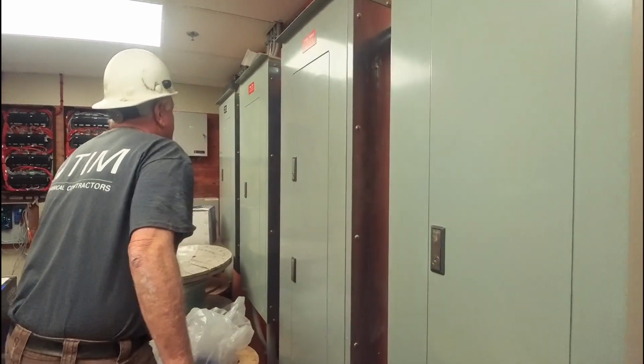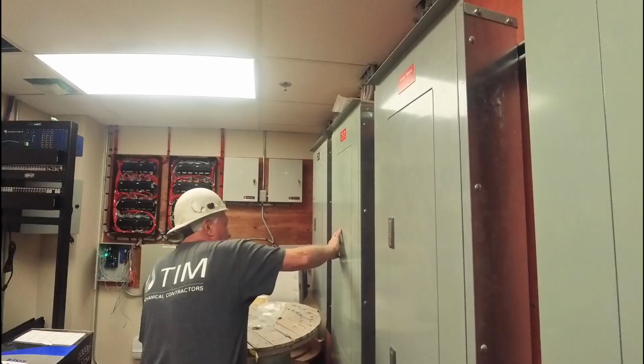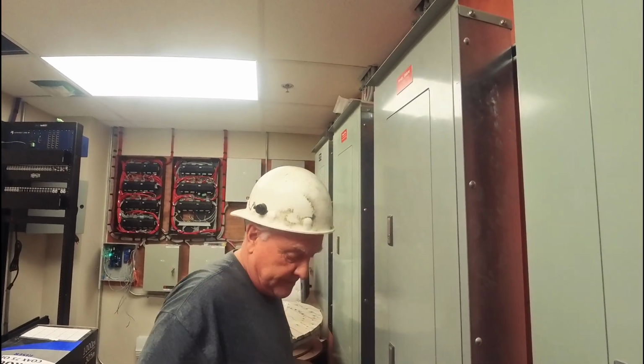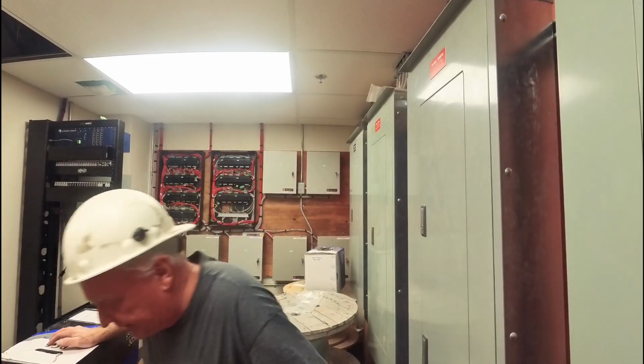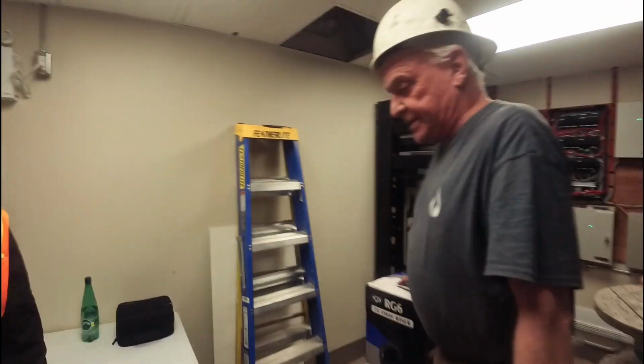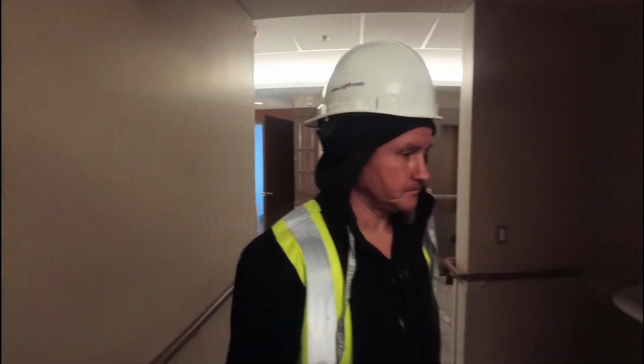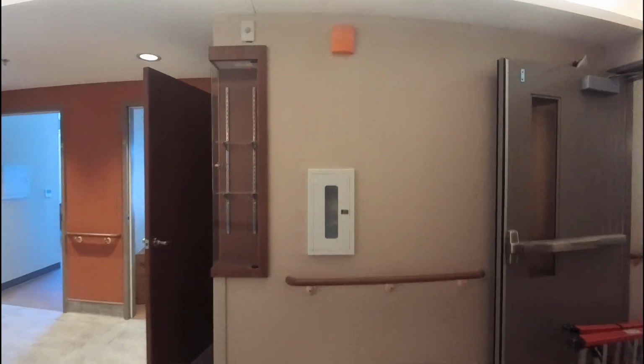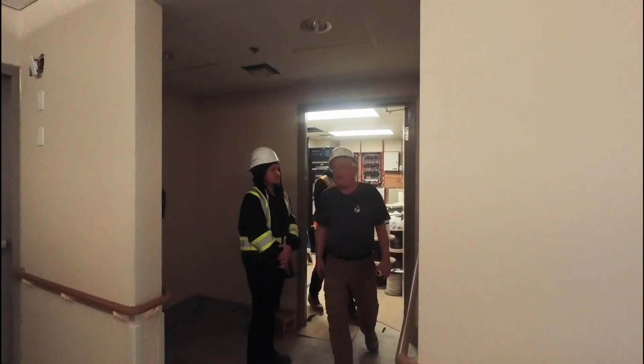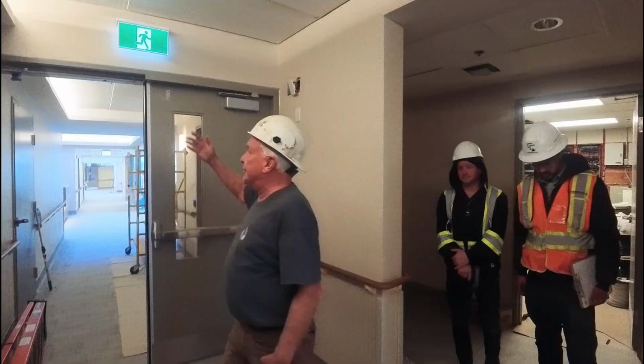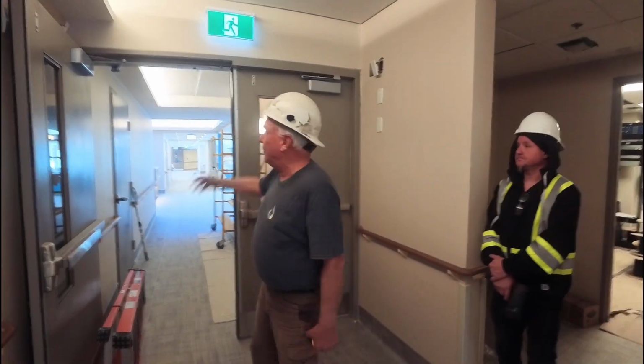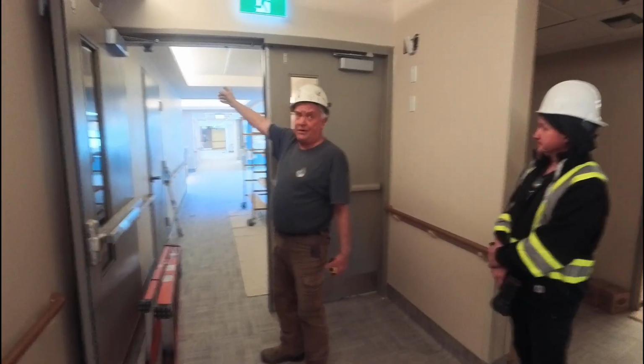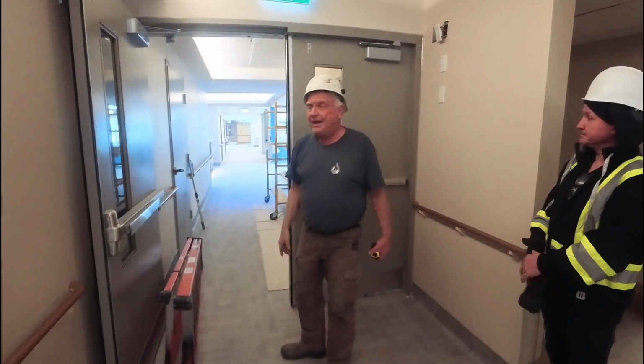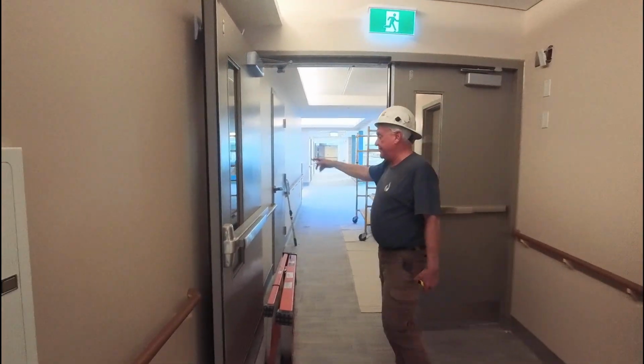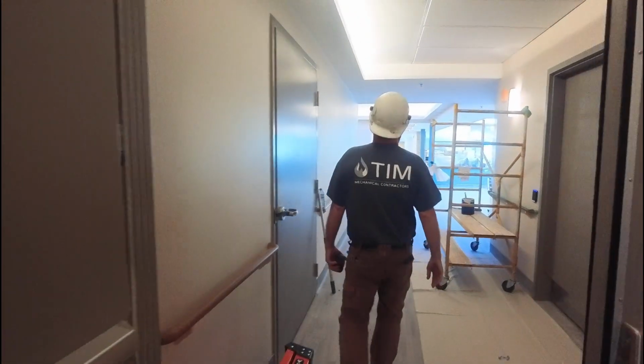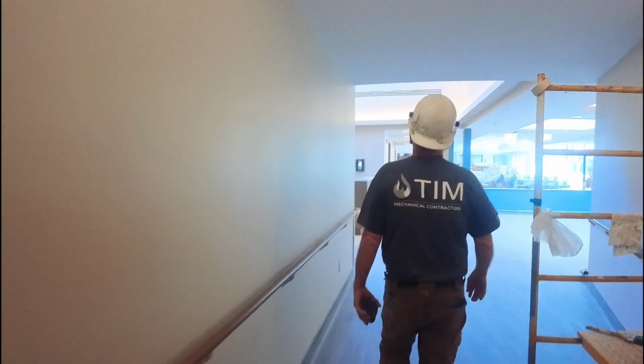I don't know if he was shutting them off in this one. Locked out though, right? It was Ryan yesterday, and I asked Derek from EMCS to shut off makeup air number 2 and 3, associated with the southeast and southwest, because I didn't want them running at full speed, because the dampers are shut. So all the air is being dispersed and fighting itself around. I thought the little nurses area was right there, and there's two diffusers there that are blowing like crazy. That's what all the noise is from out here.